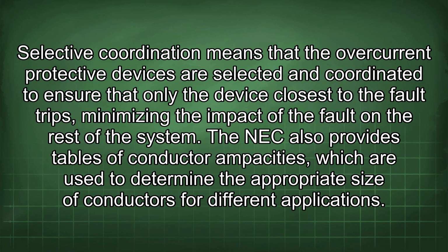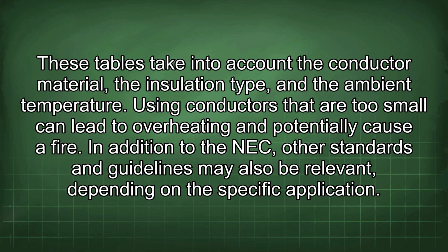The NEC also provides tables of conductor ampacities, which are used to determine the appropriate size of conductors for different applications. These tables take into account the conductor material, the insulation type, and the ambient temperature. Using conductors that are too small can lead to overheating and potentially cause a fire.